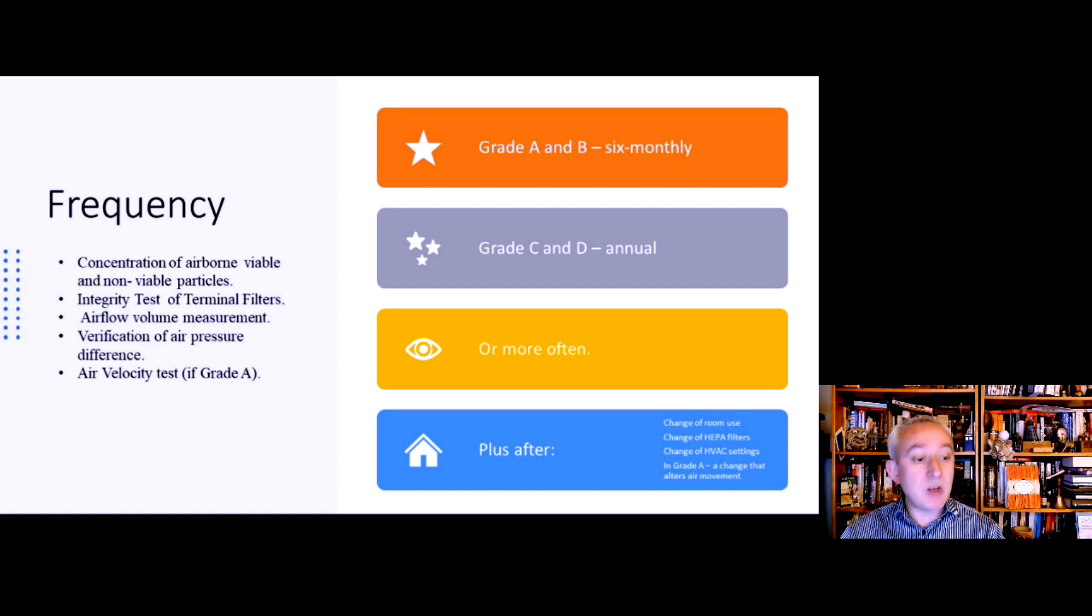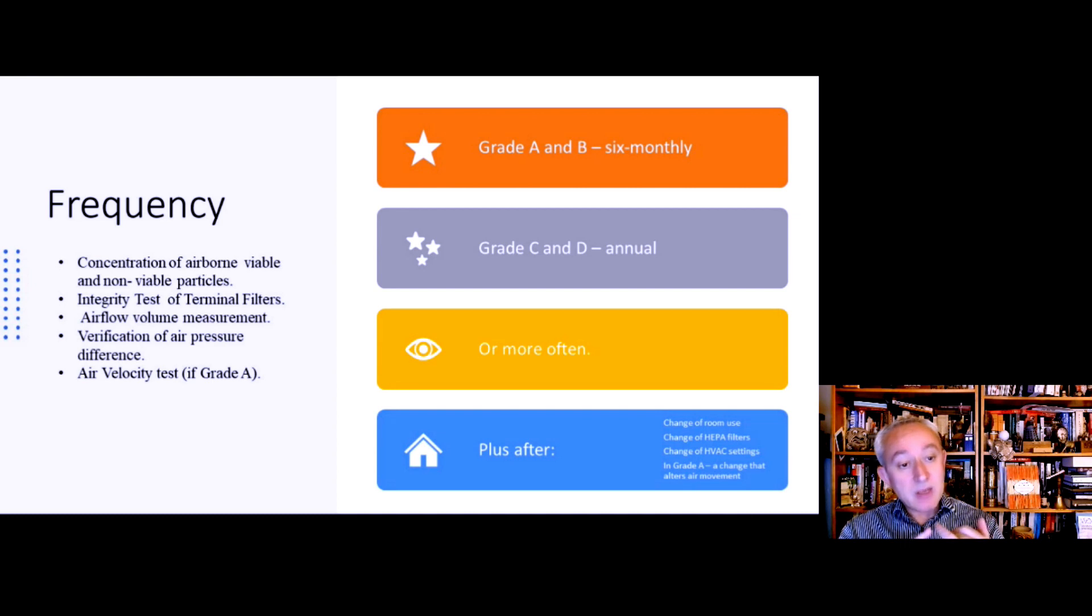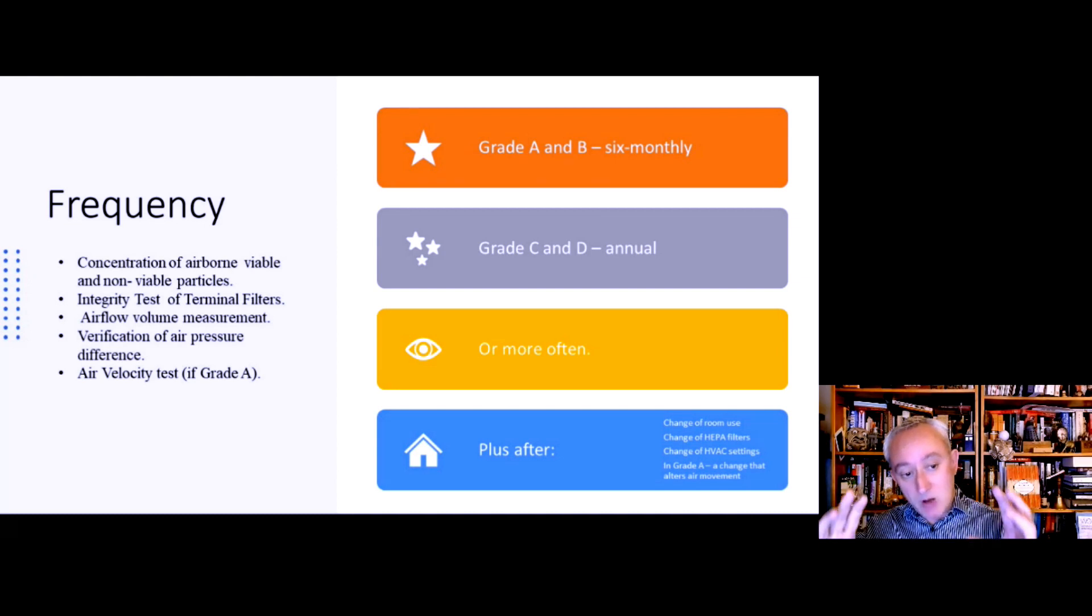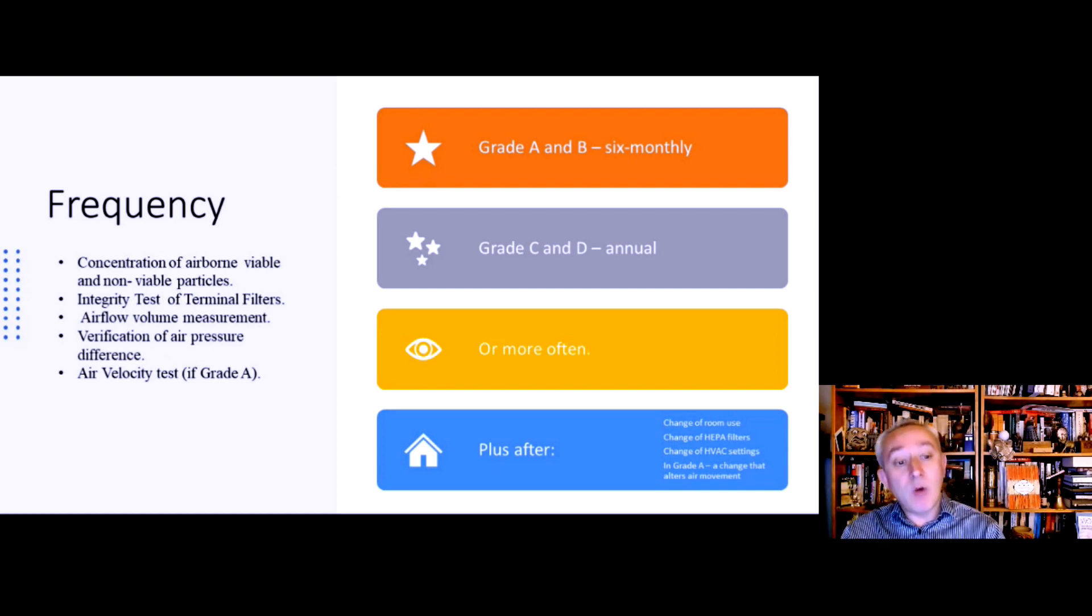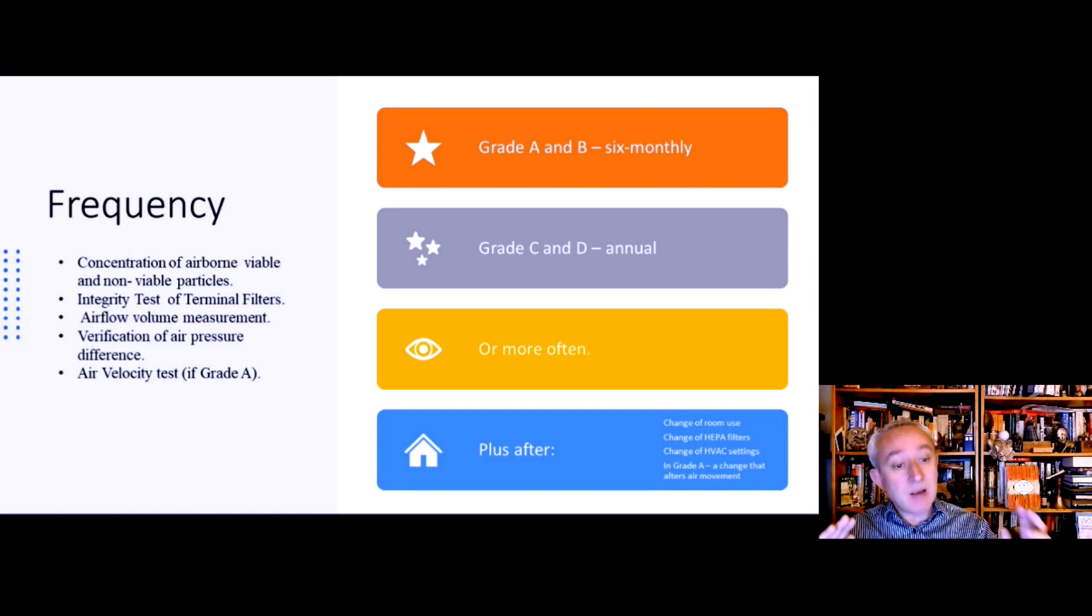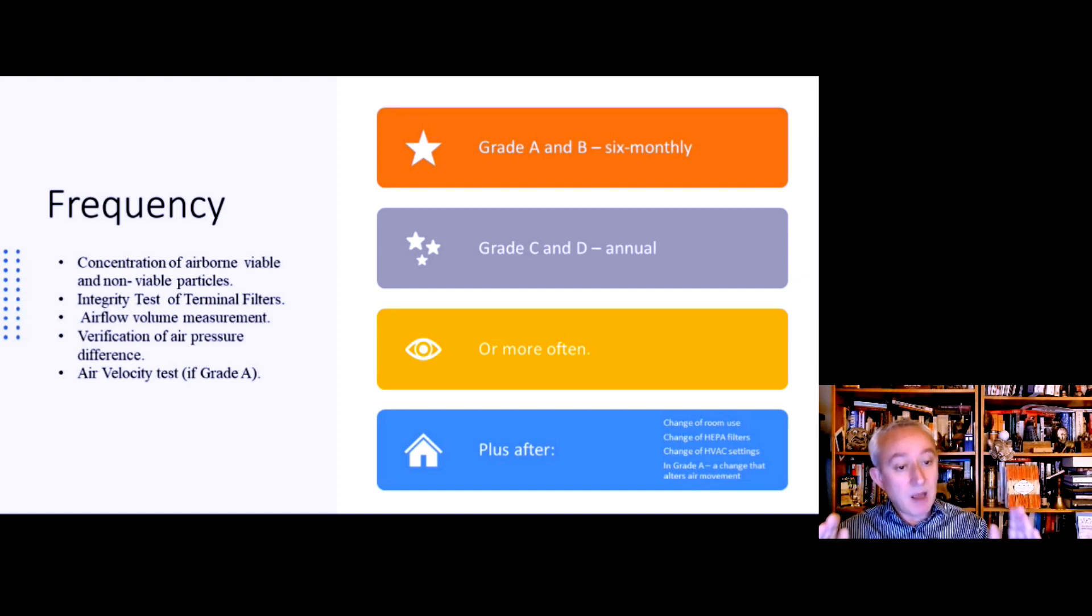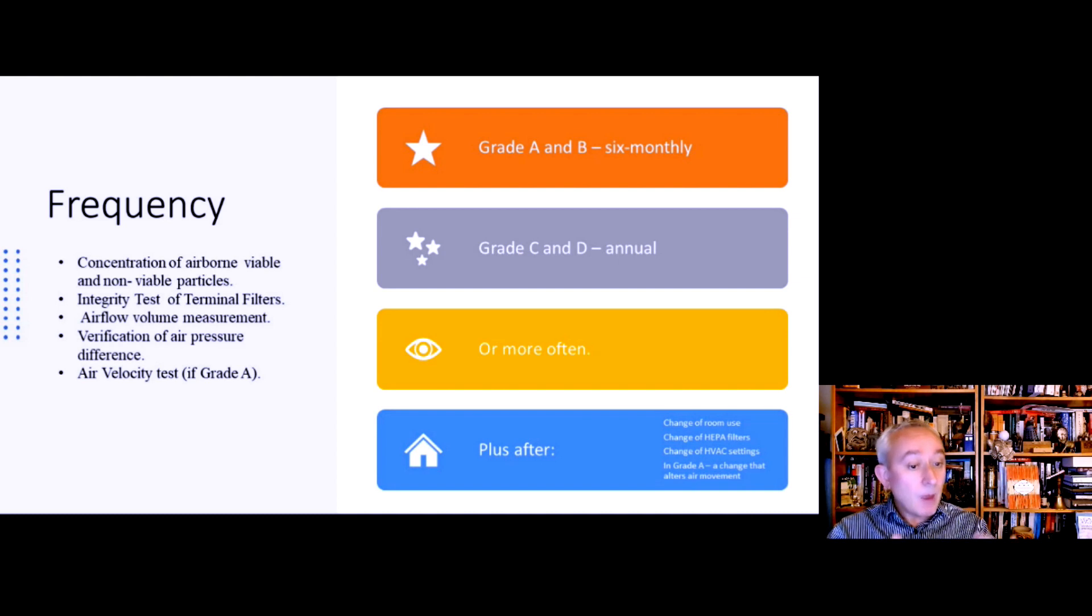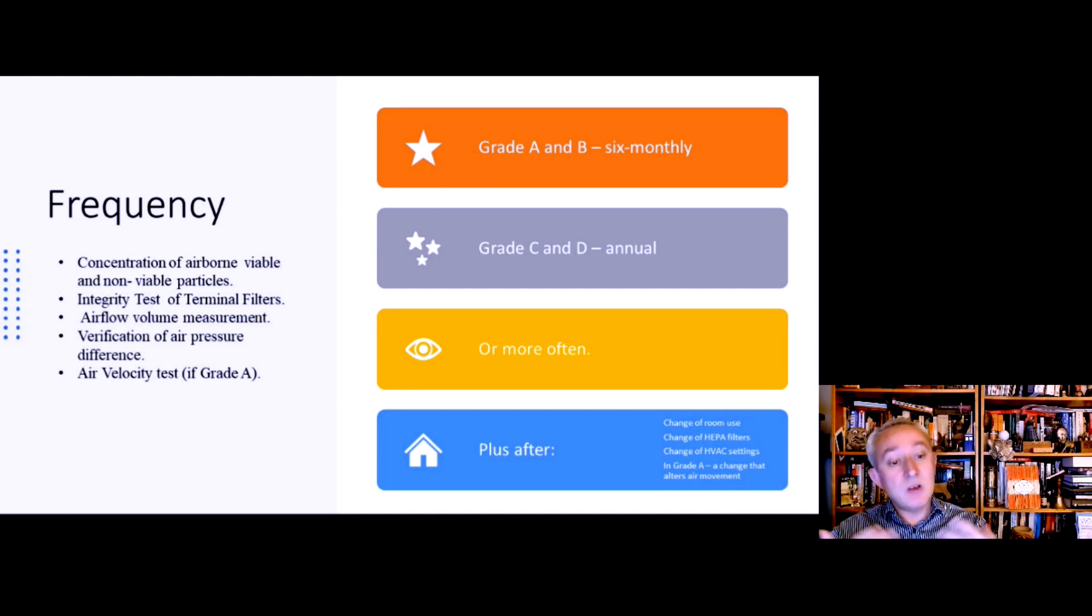The requirements for this reclassification must include the assessment of the concentration of airborne particulates—that's important because that is the measure of airborne cleanliness. Integrity testing of the HEPA filters, the terminal HEPA filters. Airflow volume measurement, because we still want to know that the air being supplied hasn't deteriorated, so we're still getting the air change rates that we desire. Verification of air pressure differentials. For grade A, the airflow velocity test. We also need to conduct the microbial classification element as well. Again, this is applying to at-rest and in-operation. So there's lots of things that need to be done every six months or once a year or if we change something critical, so there needs to be time in any production schedule to allow those operations to take place.